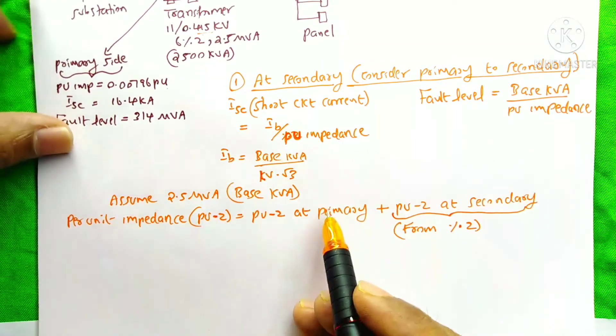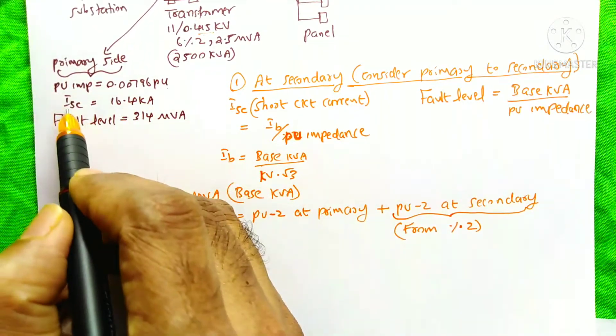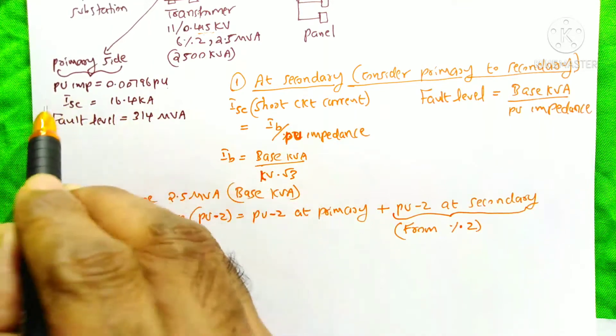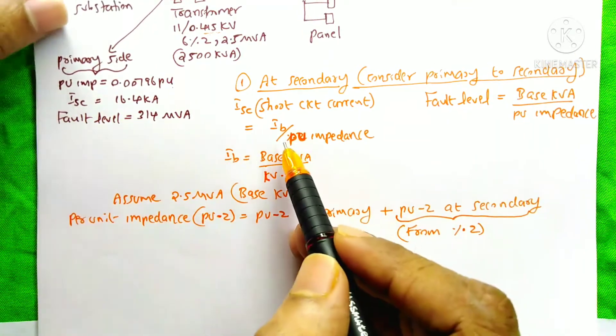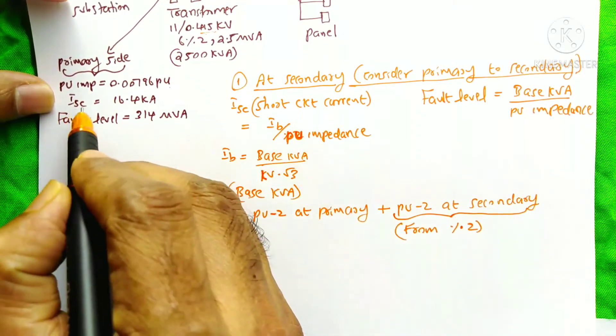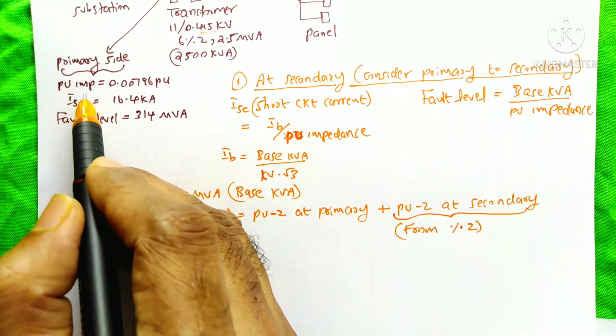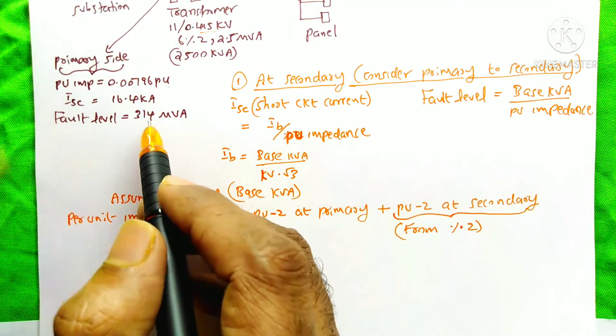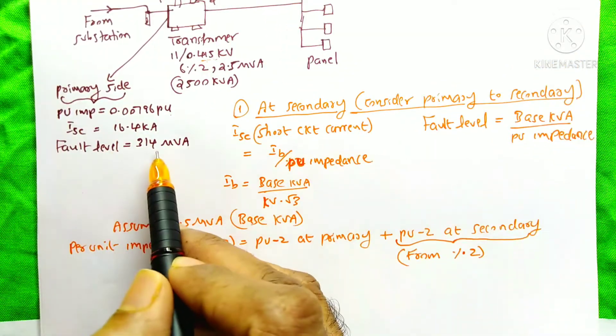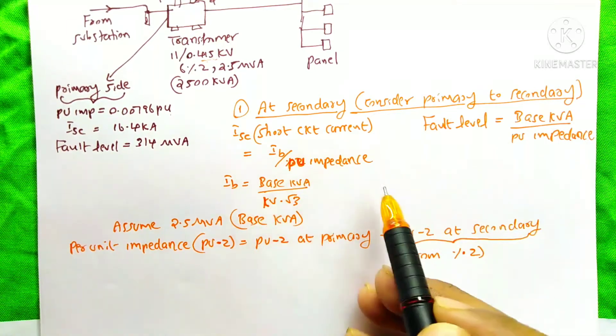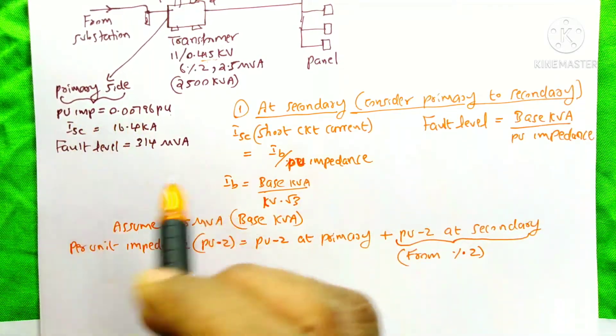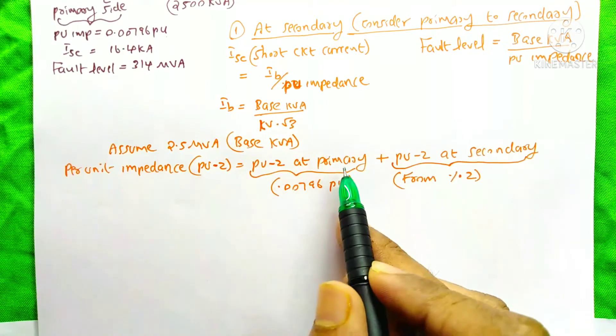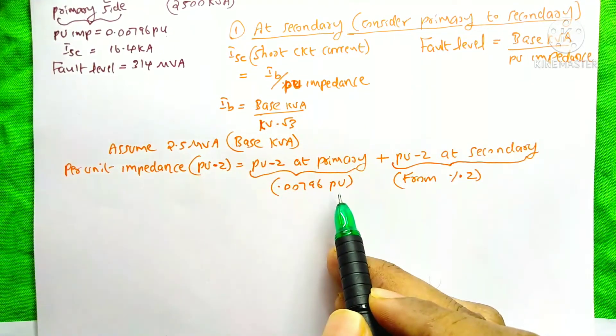If you don't have the per unit impedance at the primary, and you only have the short circuit current or fault level, you can easily find the per unit impedance using ISC equals IB divided by per unit impedance, or the fault level equals base kVA divided by per unit impedance. But here we already have this data, so we directly put this value. Our per unit impedance at the primary side is 0.00796 per unit.